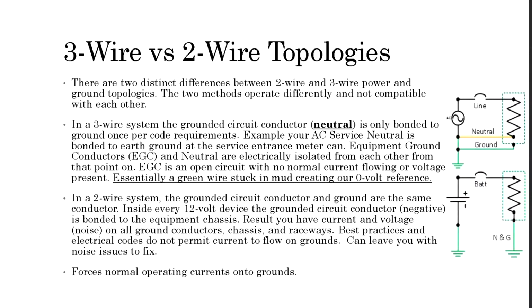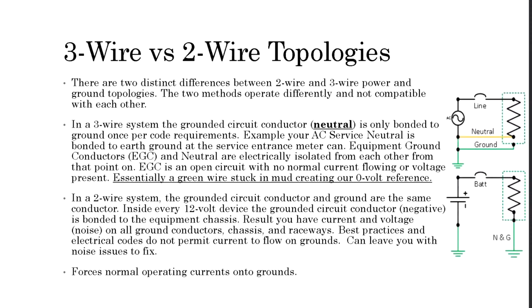Okay, let's talk about 3-wire versus 2-wire topologies. There are two distinct differences between 2-wire and 3-wire power and ground topologies. The two methods operate differently and are not compatible with each other. In a 3-wire system, the grounded circuit conductor, the neutral, is only bonded to ground once per code requirements. Example, your AC service neutral is bonded to earth at the service entrance meter can. Equipment ground conductor and neutral are electrically isolated from that point on. The EGC is an open circuit with no normal operating currents flowing or voltage present. Essentially, it's a green wire stuck in the mud, creating our 0-volt reference point.